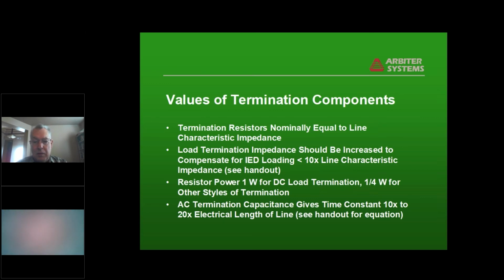Termination resistors you normally want to make equal to the line characteristic impedance. If you do that, it's a properly terminated line and there's no reflections off the end, which is where all the ugliness comes from. And the load termination impedance should be increased to compensate if the IED loads more than 10 times of what the characteristic impedance is.